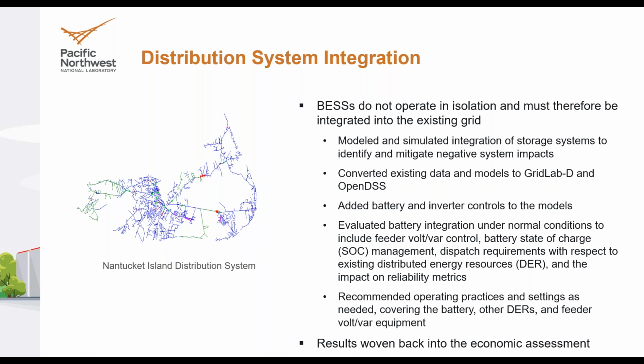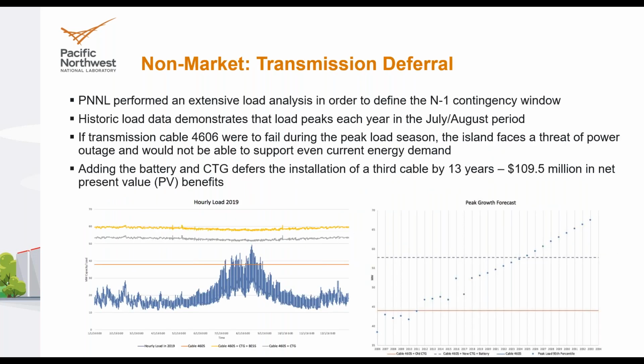We also showed that through advanced switching—feeder switching—you could really reduce the outage times, bringing it down from a 1 hour lag before addressing the outage through manual switching to as limited as 1 minute or 5 minutes. We could define the value associated with that and the cost, so you could determine whether or not the investment made sense.